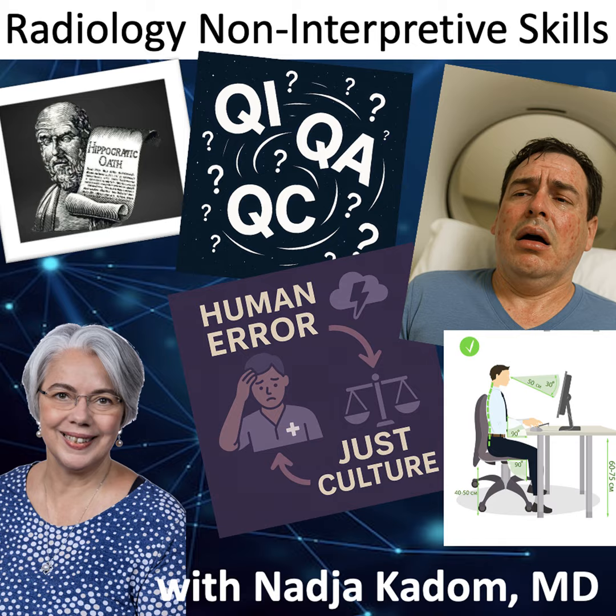And maybe as a last point, can you talk a little bit about monitoring equipment like EEG leads and other things? Can those go in the MRI scanner? Yeah. So we have specific equipment in the MRI room that is permissible to be actively on the patient while scanning. Anything from the floors, those little leads, they have caused burns. And a lot of the times, if a patient gets picked up, for example, by an emergency EMT, they're monitoring them and they're putting leads all over their bodies. So that's why the visual check that I had mentioned earlier is very important, especially in a trauma hospital or any hospital, really, just to check the patient's body to make sure they don't have these leads.